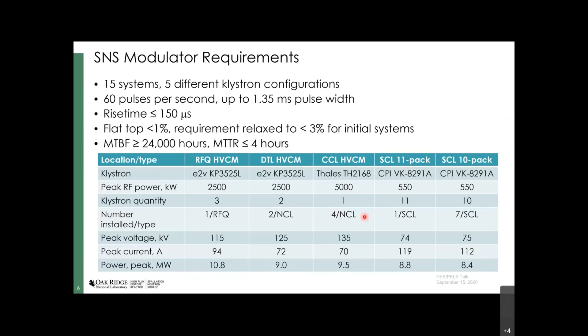We have an initial flat top requirement of 1%, but because of some problems in the early systems, that was relaxed to about 3%. And the mean time between failure, the goal originally was 24,000 hours with a mean time to repair of 4 hours, excuse me. So you can see down here, peak powers range from as high as 11 megawatts out on the modulator down to about 8.5, depending on where you are in the system. And we have anywhere from 1 klystron per modulator all the way up to 11 klystrons per modulator, depending on the load configuration.